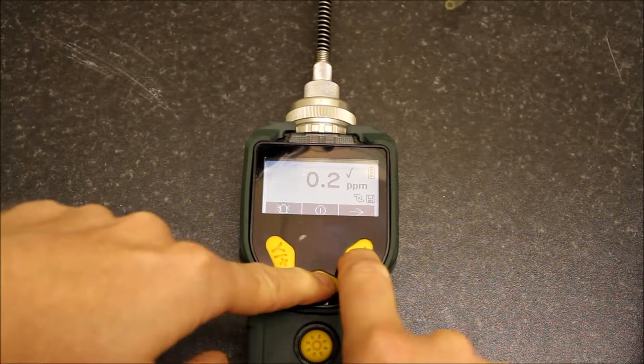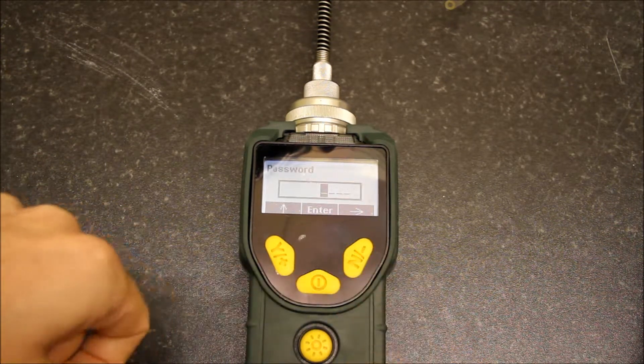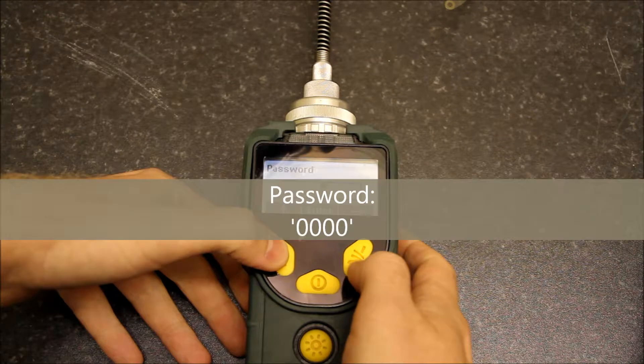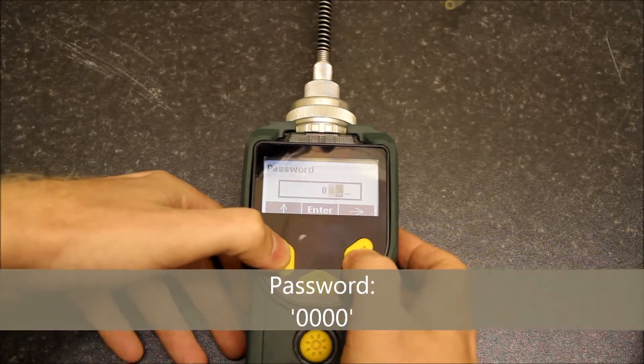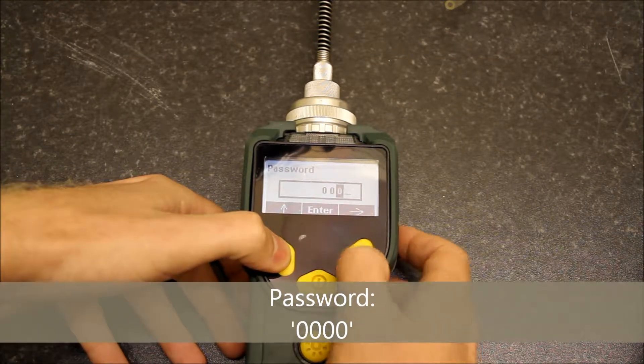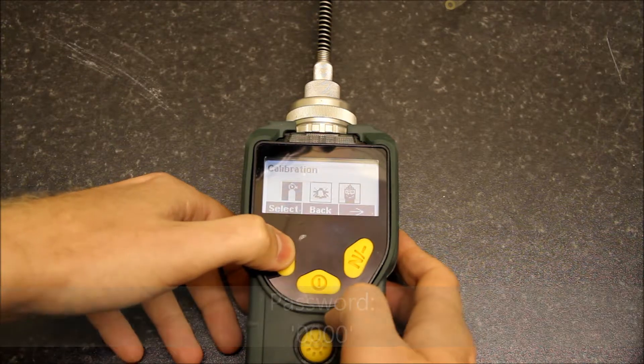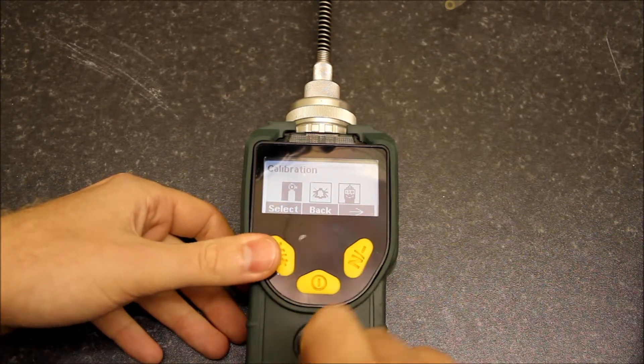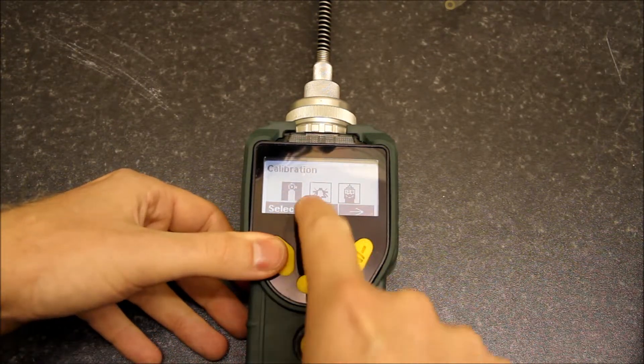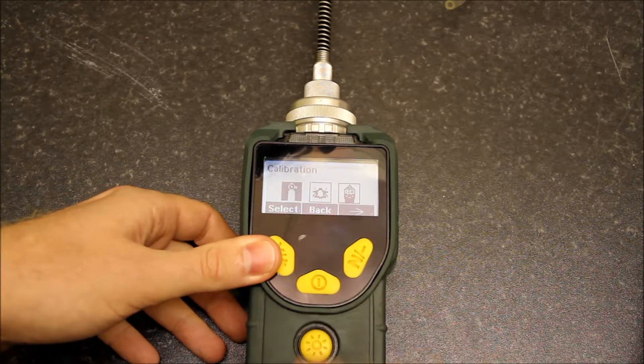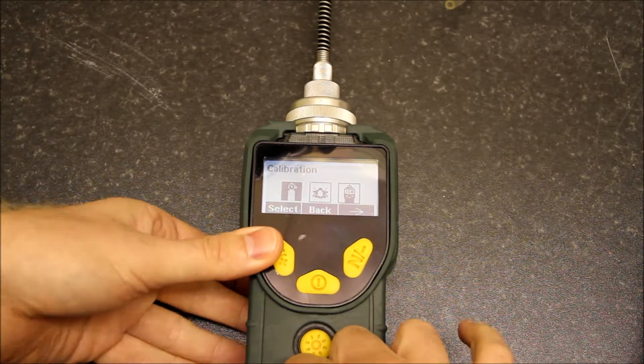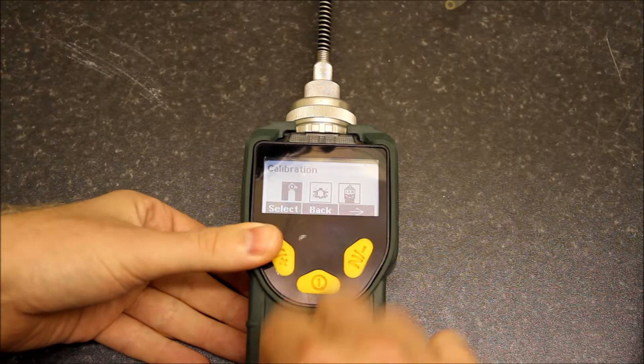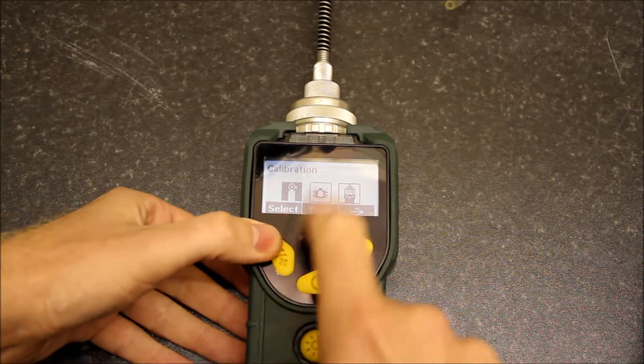If we press power and no, we can get into the calibration menu. It's asking for a password here, so press zero, zero, zero, and zero. We've got a few menus: calibration menu, alarms menu, and monitor setup. For us, the only real menus we're using are the calibration menu and the alarms menu.